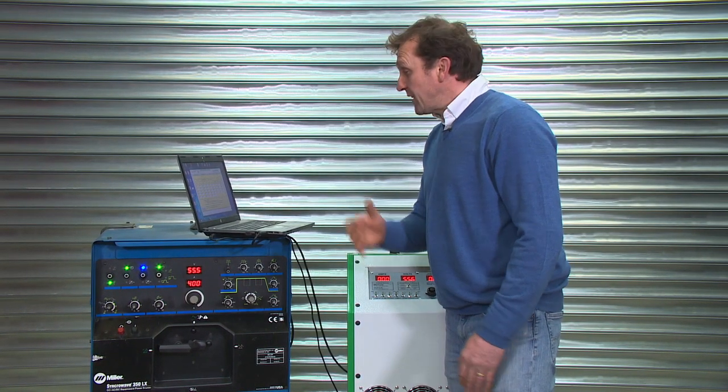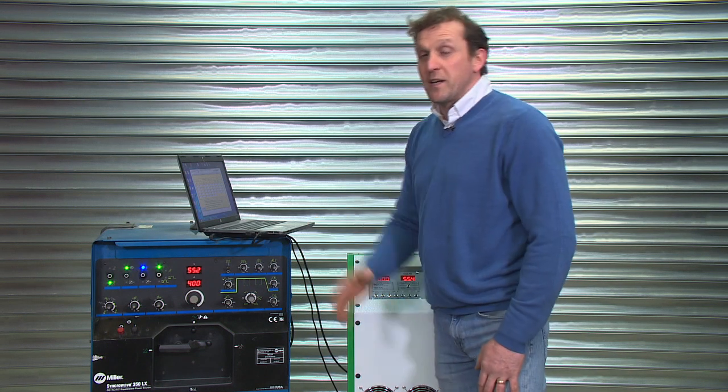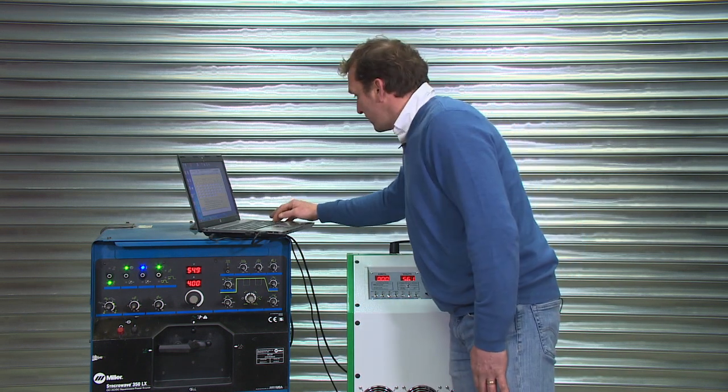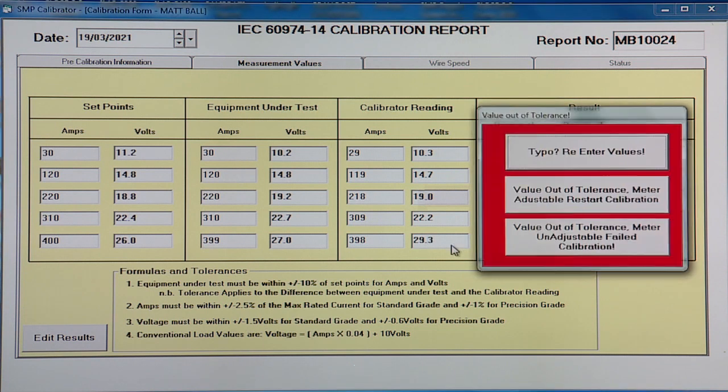And then just for training, instead of putting 26.3, if we put 29.3, a fail value in, the program will flag up immediately there for you. Was that a typo? Is that an error on my behalf? Is the value out of tolerance? But we can adjust the meter. If that was possible, we'd adjust the meter back into tolerance and restart the process again. Because obviously, all the values will have changed across the range.